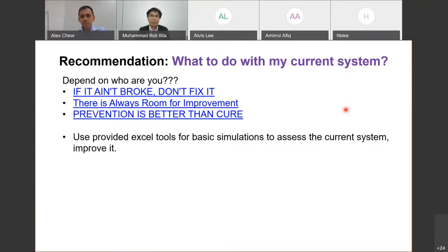So what you can do is, I provide you with the Excel tools, so you can do some basic simulation to assess the system you have. For example, you check based on the calculation you have. Let's say based on the calculation you have a volume of 50 cubic meters, but in reality you have an activated sludge or biological system that runs at a volume of 100. Basically that means you are over designed. When you over design, you have an opportunity to increase the treatment capacity.